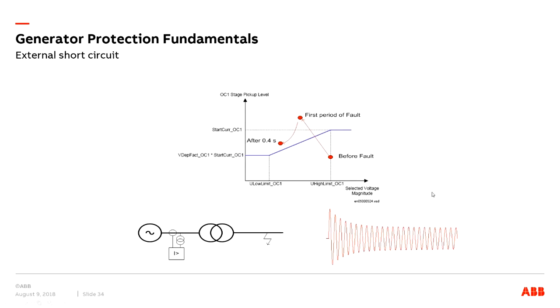So in the case of an external short circuit, the generator overcurrent protection serves as a backup protection. If a normal overcurrent protection is used, as I mentioned, there is a risk that the current will be reduced to a value less than the set trip level before the set time delay has elapsed, and the protection will thus not give a required trip in that case. So with the voltage dependent overcurrent function, the trip can be guaranteed. Okay, you can see that in this curve here.